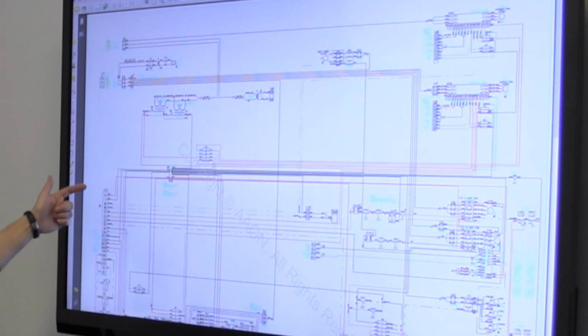And so here's your terminal strip again. Automated logic would be on this side of the terminal strip, and everything else is Aeon. So if you ever look at that terminal strip, I think the top side is Aeon, the bottom side is automated logic. Automated logic installed isolation relays on everything, so they have their own power, and they're operating their relays so that we can use our own power to pull in our contactors and things like that, so that the two are separate.